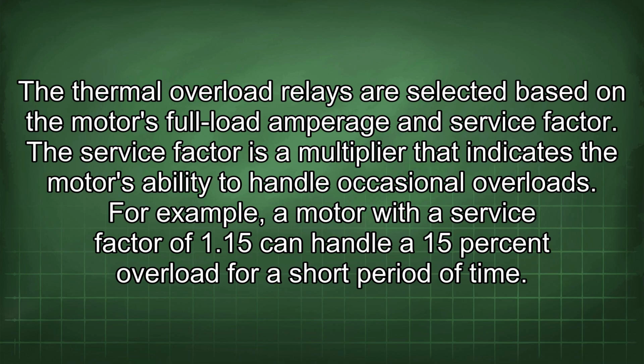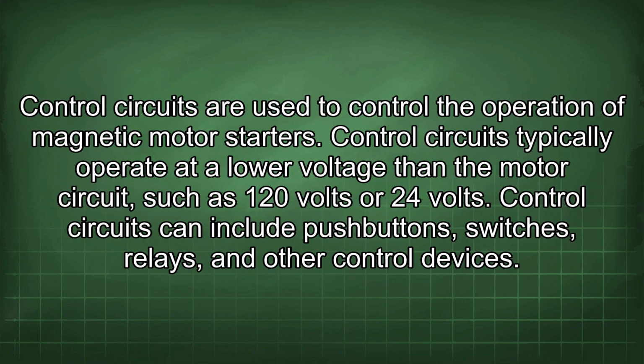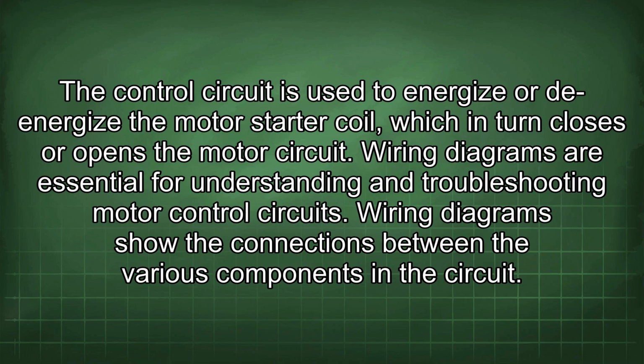The service factor is a multiplier that indicates the motor's ability to handle occasional overloads. For example, a motor with a service factor of 1.15 can handle a 15% overload for a short period of time. Control circuits are used to control the operation of magnetic motor starters. Control circuits typically operate at a lower voltage than the motor circuit, such as 120 volts or 24 volts. Control circuits can include push-button switches, relays, and other control devices.